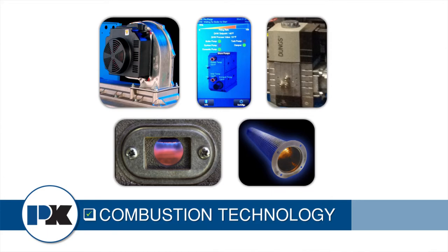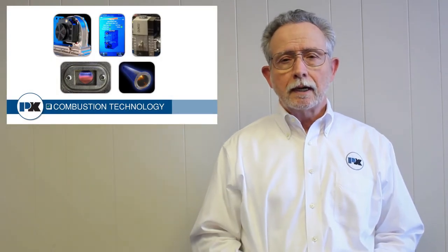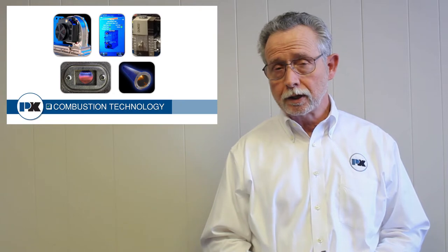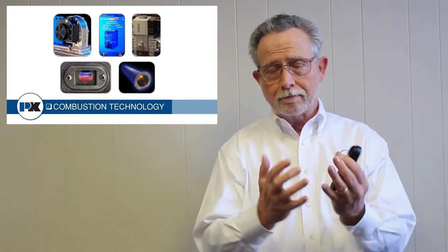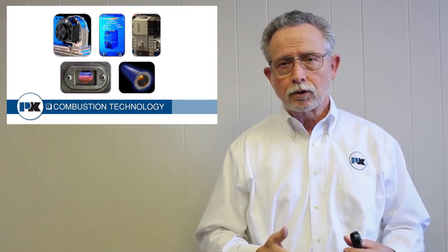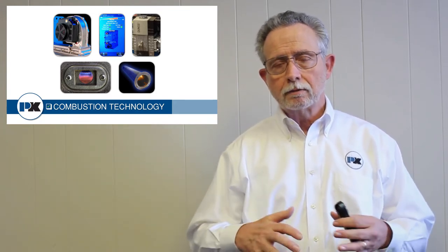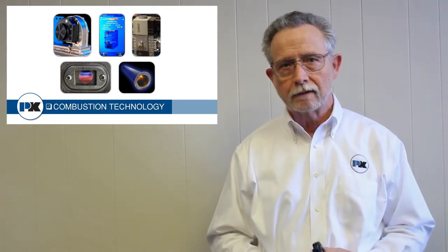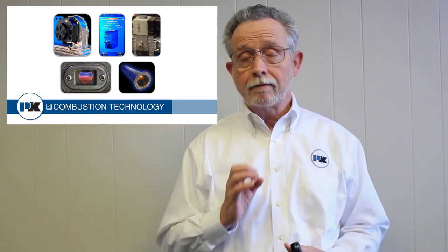We're going to use an induced blower, a double solenoid gas valve — it's a zero-governing negative pressure gas valve — and a ported stainless steel burner that has a wrapped stainless steel mesh around the outside. This gives us increased combustible mixing and also flame retention on the burner itself.